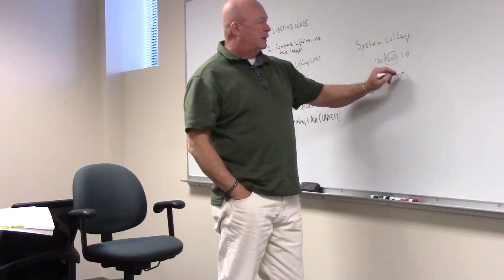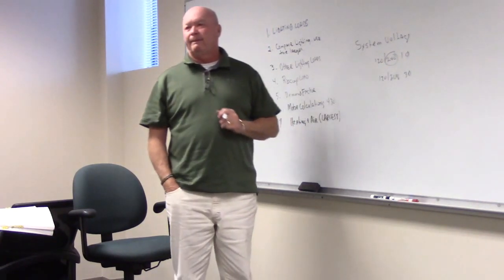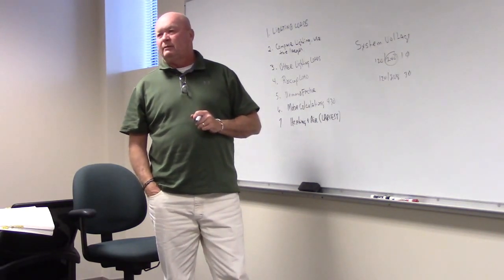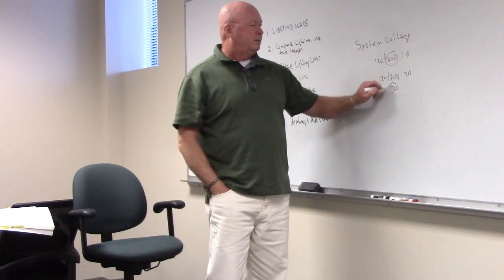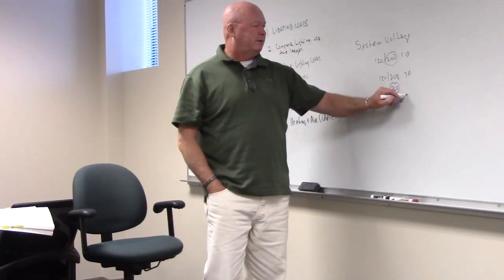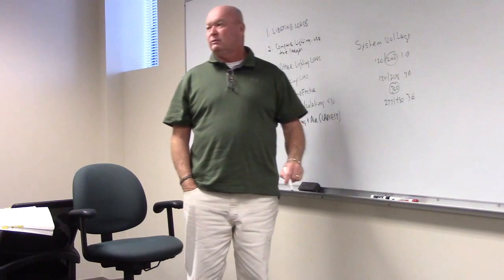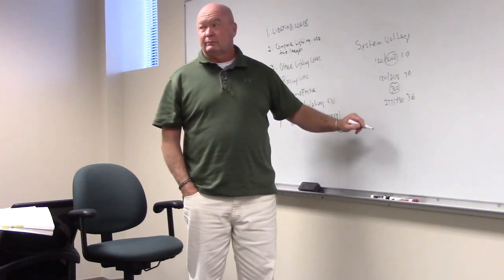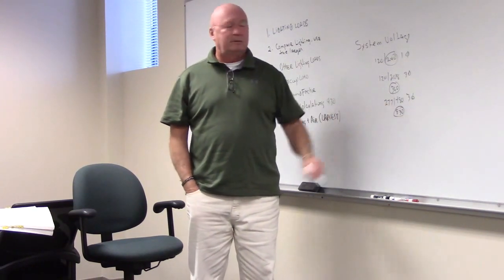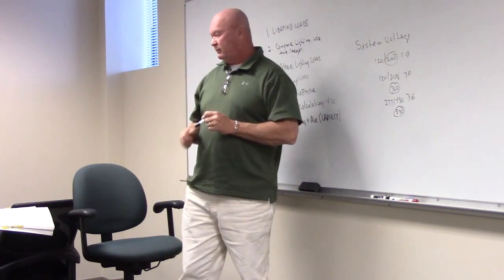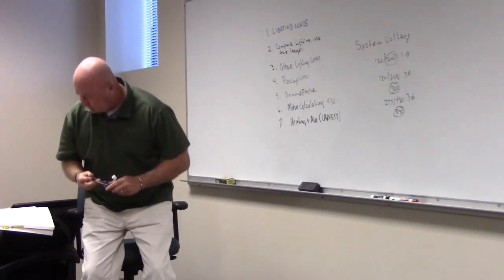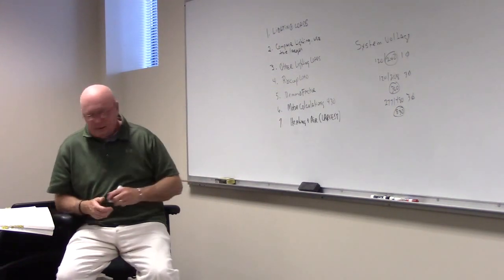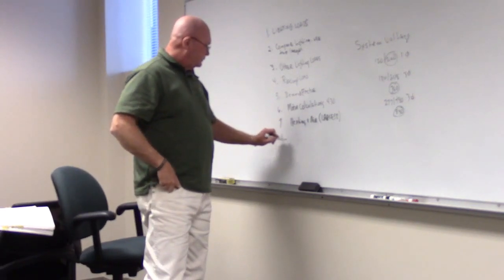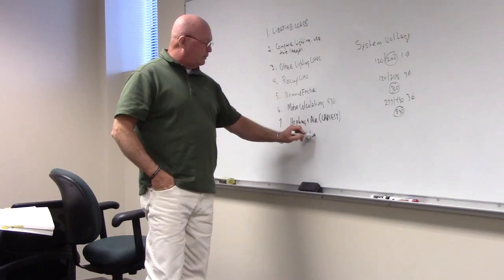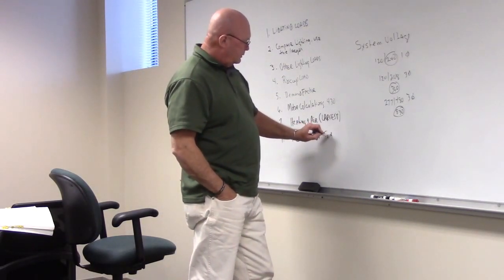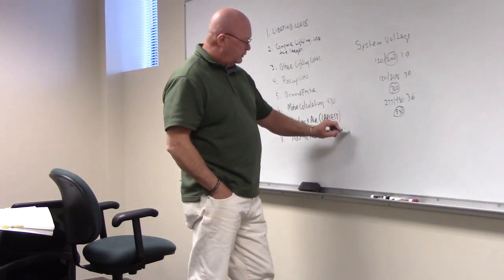What is your system voltage for 120/208 three-phase? 208 times what? Square root of 3, which is what, 360? How about 277/480, three-phase? How much? 480 times 1.732 equals what? Maybe 830, see if I'm right. Close enough. The system voltage, that's what we're going to use. So we've done all this. Number 8 is add all the loads, and system voltage is important.